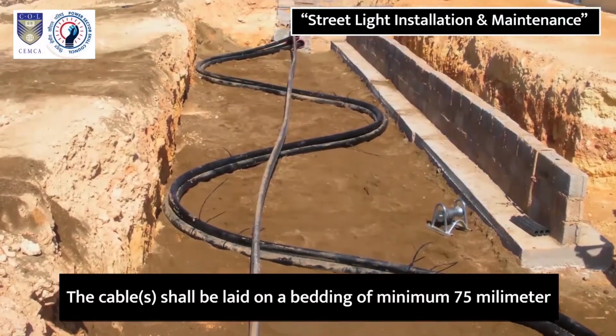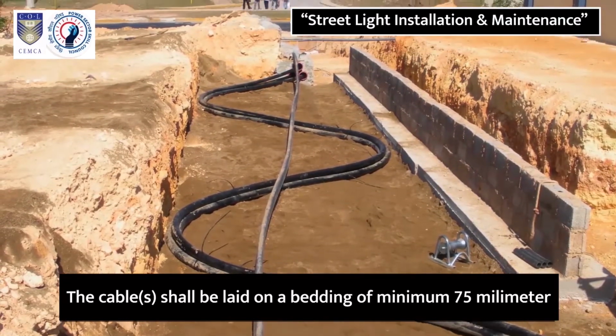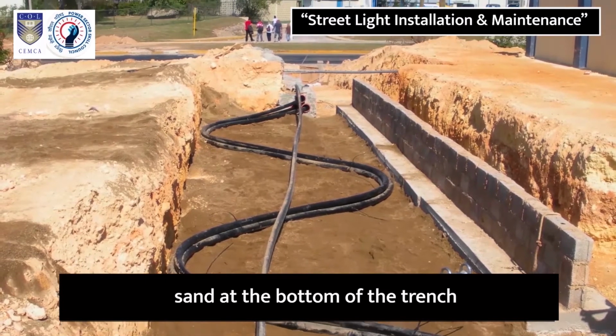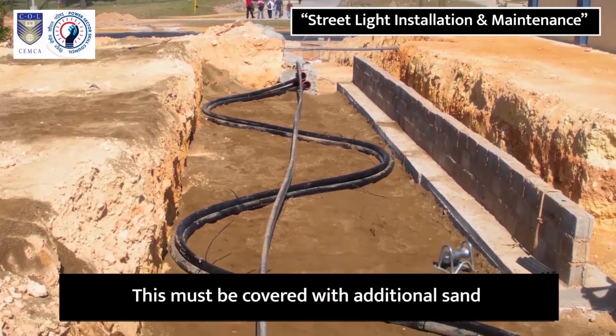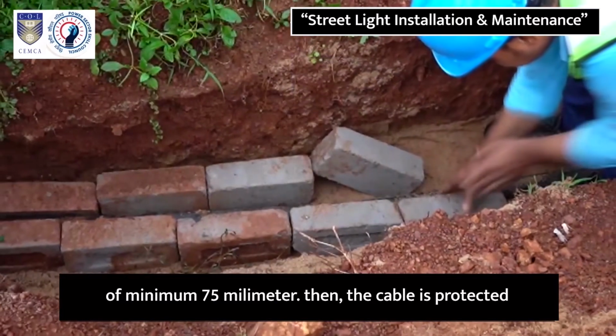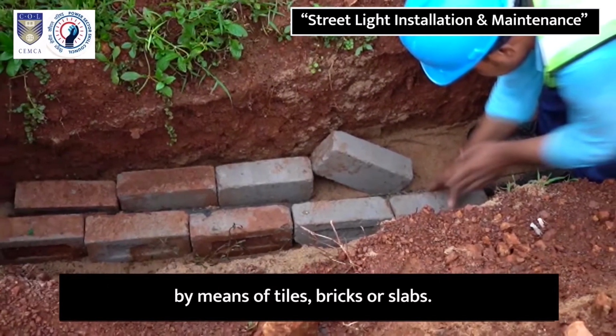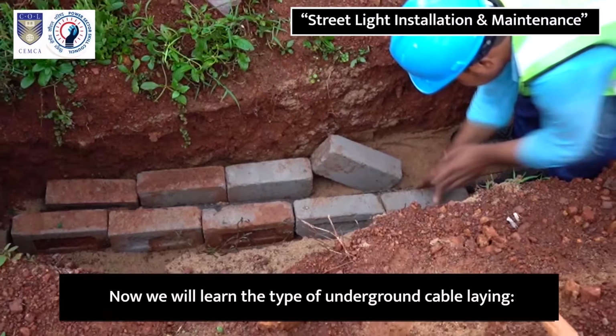course of the work. The cable shall be laid on a bedding of minimum 75 mm sand at the bottom of the trench. This must be covered with additional sand of minimum 75 mm. Then the cable is protected by means of tiles, bricks, or slabs.